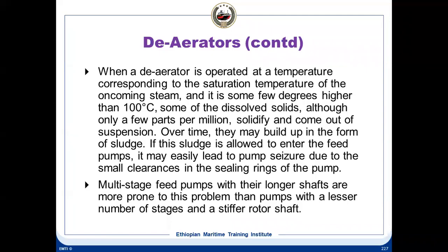And this can only happen over a long period of time. But it is something to watch out for, that some of this dissolved solids of your heating coil, etc., can come out in the condensate, and then over a period of time it forms sludge. And then once it enters the feed pump, since for the high pressure feed pump the clearances are very, very fine, the pump seizure can occur.